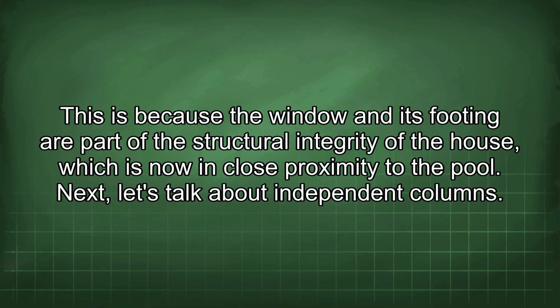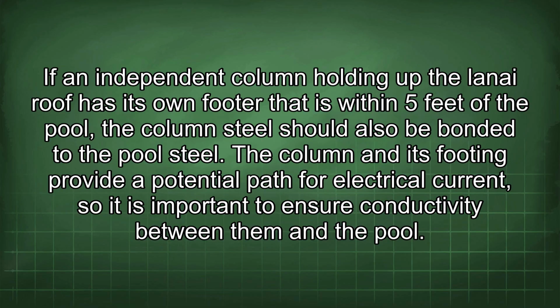Next, let's talk about independent columns. If an independent column holding up the lanai roof has its own footer that is within 5 feet of the pool, the column steel should also be bonded to the pool steel. The column and its footing provide a potential path for electrical current, so it is important to ensure conductivity between them and the pool.